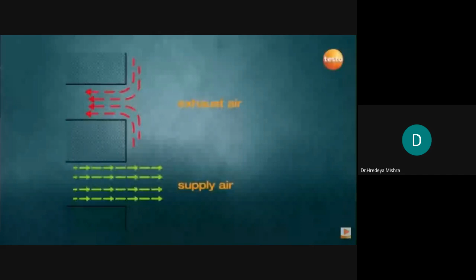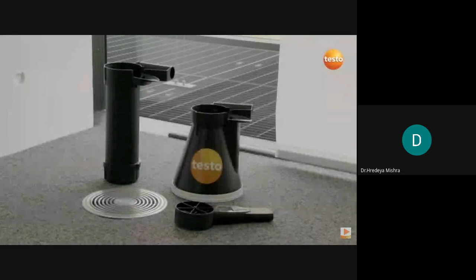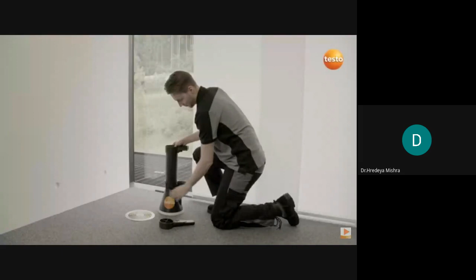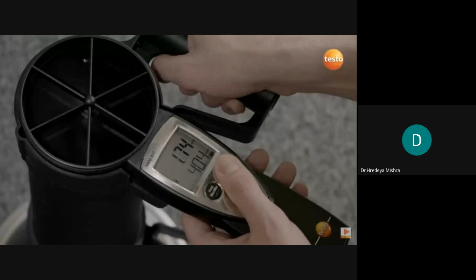This is how you measure properly at the swirl outlets. Measuring the volume flow accurately at swirl outlets is often a challenging task because the supply air is fed into the room in a circular motion, making an accurate measurement difficult. Why is that? Vanes can only record the flow accurately if the airflow hits the vane vertically. The flow straightener ensures that the airflow passes over the vanes in a single direction. So students, you are able to see that when the airflow is vertical, then we can use this device and measure the reading of the airflow rate of this system.